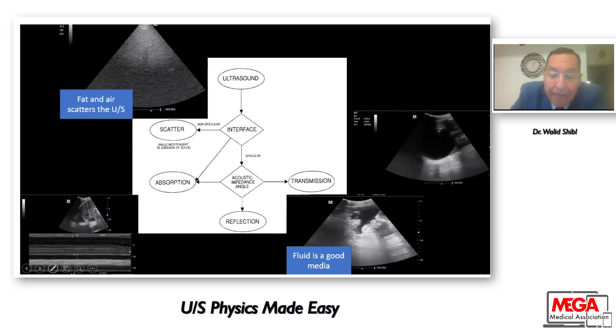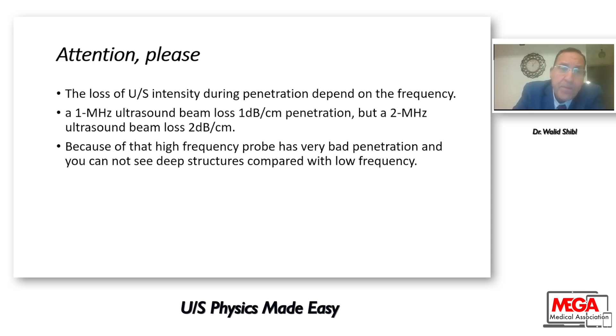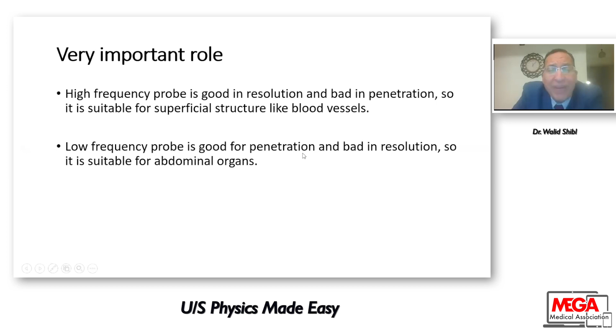And attention, please. The loss of ultrasound intensity during penetration depends on the frequency of the probe. A 1 megahertz probe will lose 1 decibel per centimeter of penetration. But 2 megahertz will lose 2 decibel. So the high frequency probe with 15 megahertz will lose 15 decibel with each centimeter. Because of that, the high frequency probe has very bad penetration. Don't examine the heart or the lung with a high frequency probe, but you need it to examine superficial structures like blood vessels. And a very important rule, you need to know: high frequency probe is good in resolution but bad in penetration. Low frequency probe is good for penetration but bad in resolution.